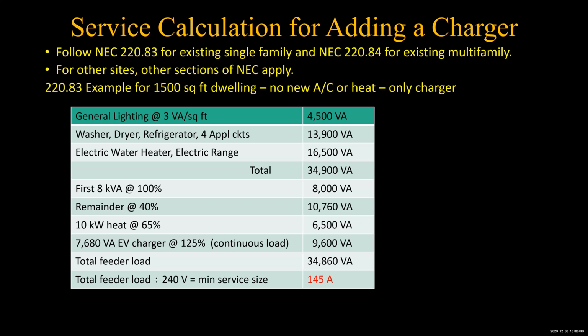Throw in your electric water heater, your electric range, another 16,500, you're up to 34,900. Take your first 8 kVA at 100%, and this because we're going to add to this thing, so then we can use this calculation. First 8 kVA at 100%, there's 8,000, and then subtract that 8 kVA from 34.9 and take 40% of the result of that, and you get 10,760.